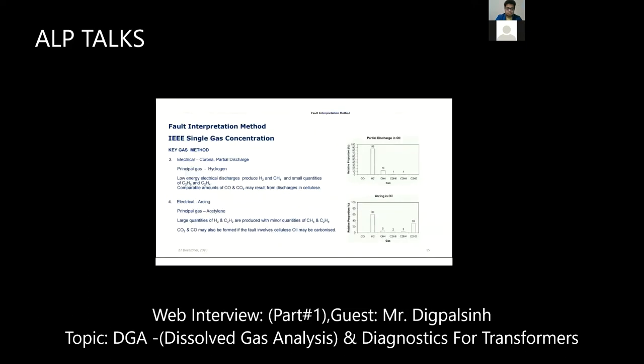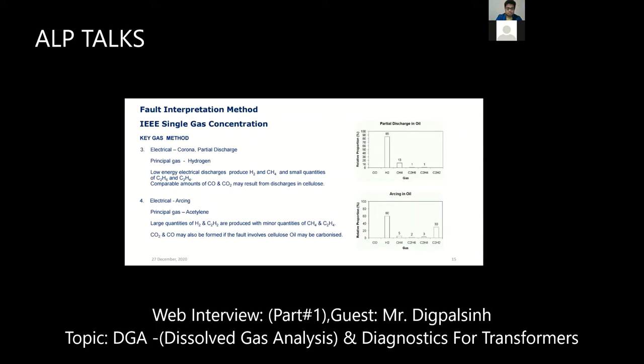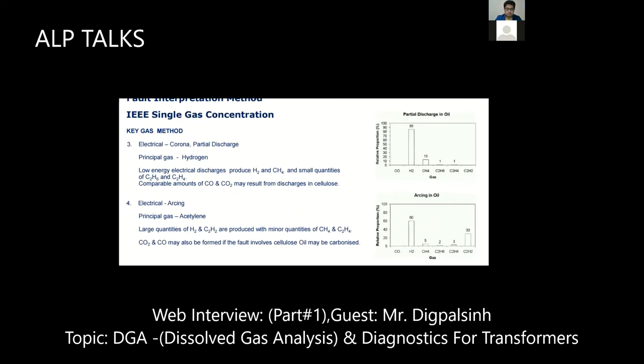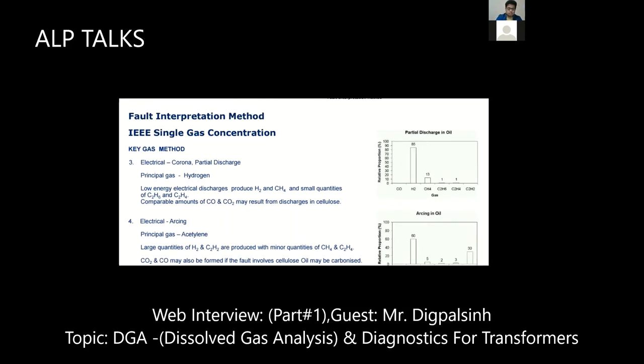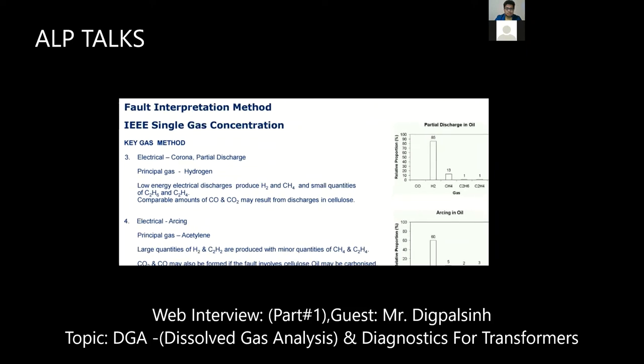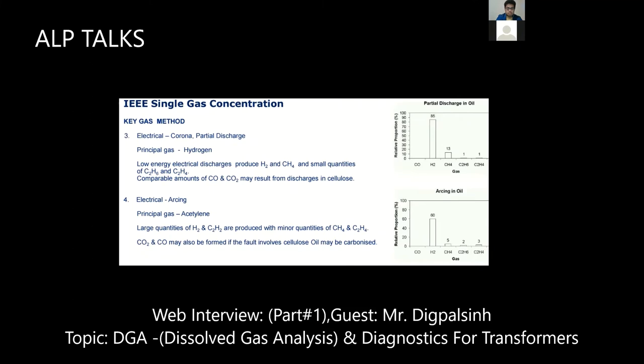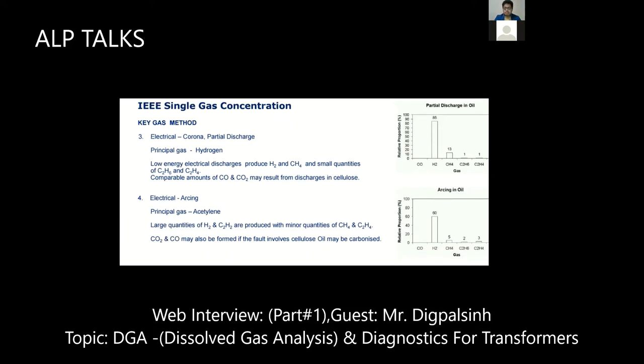So in the key gas method, third is partial discharge, or you can say corona. Hydrogen will be the principal gas for this reason. If you do DGA of the transformer oil and you find hydrogen is beyond its IEEE or IEC defined limit, then you can say it is partial discharge. In that case, low energy electrical discharge produces hydrogen with methane, and you can find some minor quantities of C2H6, ethylene and ethane also. CO and CO2 will be there, but I don't think it is necessary for this particular case. In that case, you have to combine it with thermal cellulose and partial discharge.